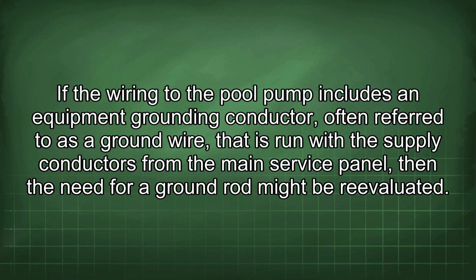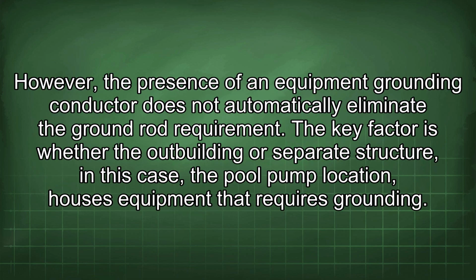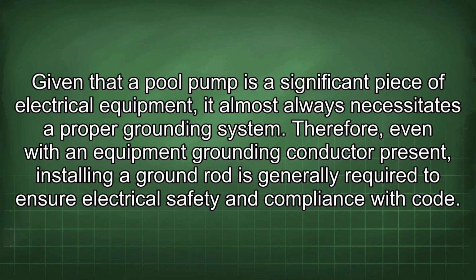If the wiring to the pool pump includes an equipment grounding conductor, often referred to as a ground wire, that is run with the supply conductors from the main service panel, then the need for a ground rod might be re-evaluated. However, the presence of an equipment grounding conductor does not automatically eliminate the ground rod requirement. The key factor is whether the outbuilding or separate structure, in this case the pool pump location, houses equipment that requires grounding. Given that a pool pump is a significant piece of electrical equipment, it almost always necessitates a proper grounding system. Therefore, even with an equipment grounding conductor present, installing a ground rod is generally required to ensure electrical safety and compliance with code.